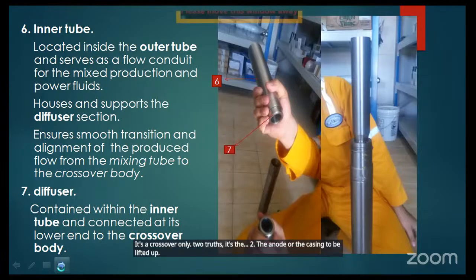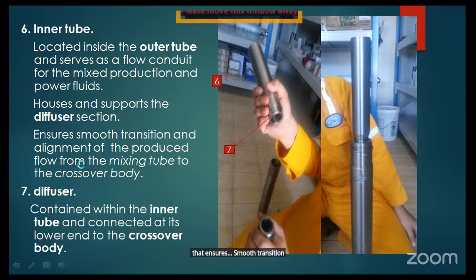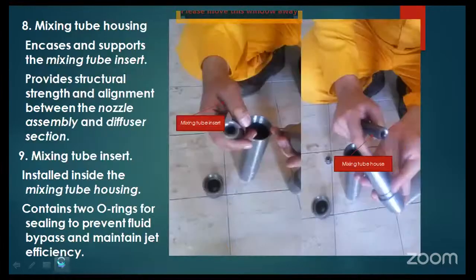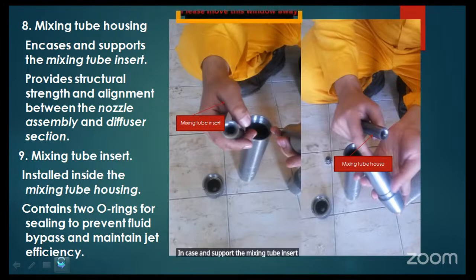That ensures smooth transition and alignment of the produced flow from the mixing tube to the crossover body. The diffuser is contained within the inner tube and connected at its low end to the crossover body. Up. We are going from down up. The mixing tube housing encases and supports the mixing tube insert, provides structural strength and alignment between the nozzle assembly and diffuser section.